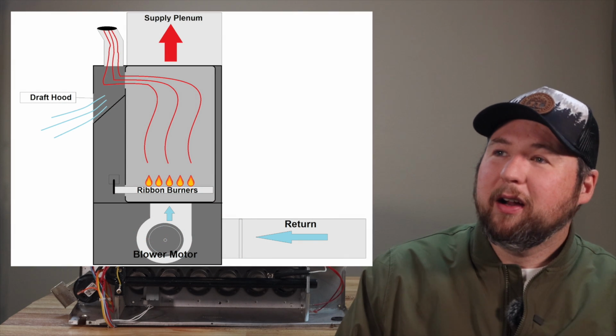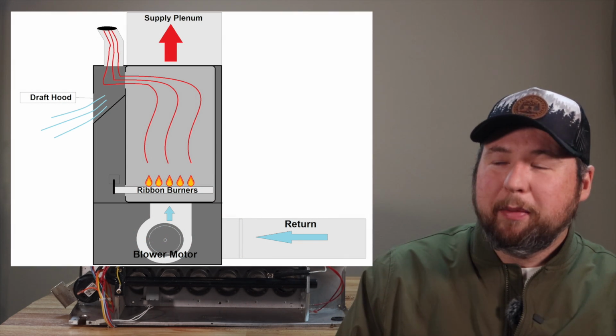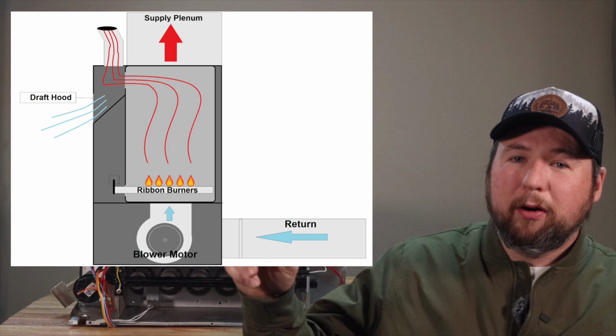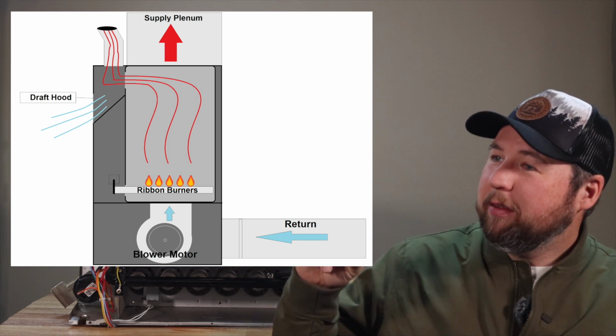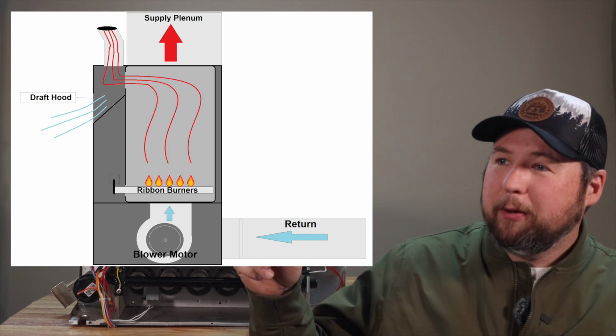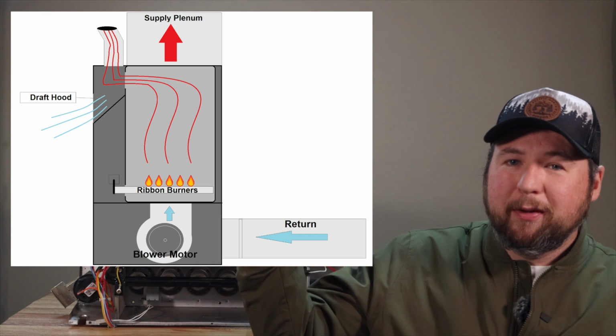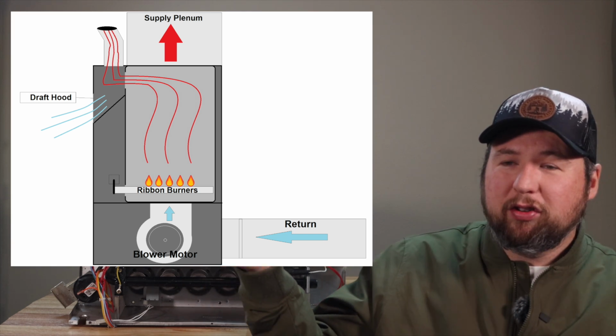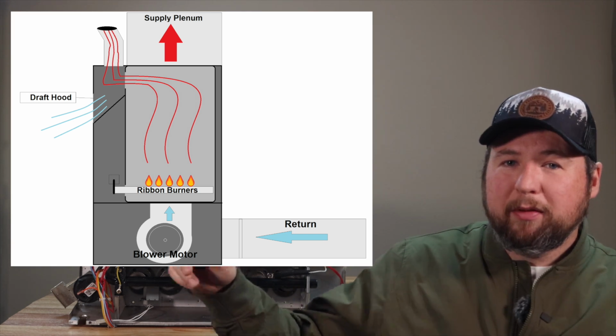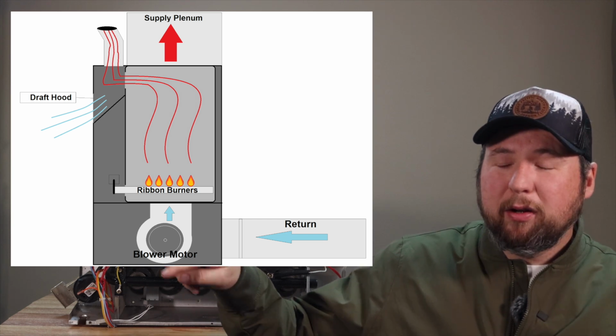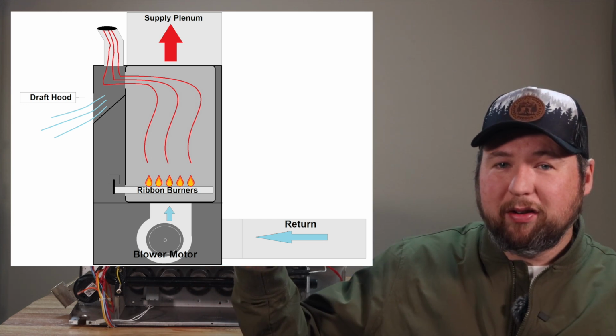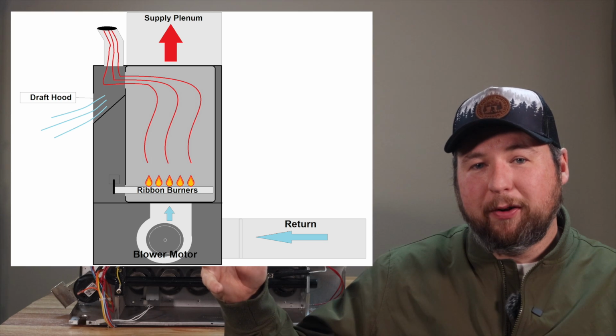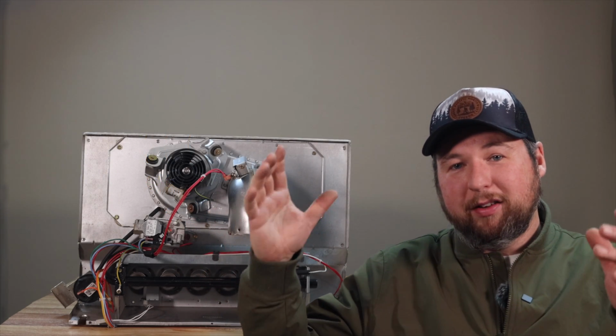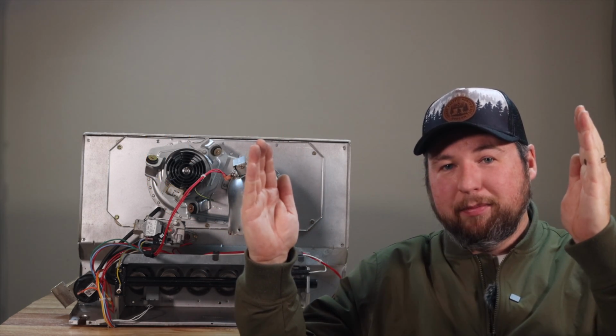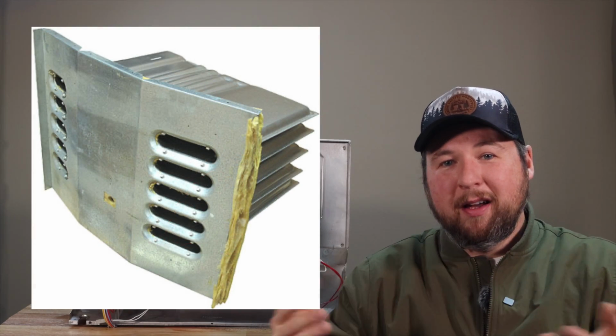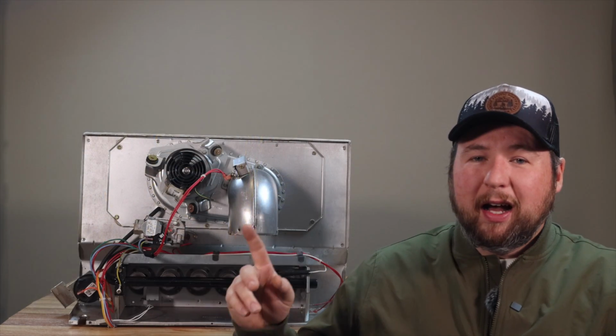So as you can see here, the natural draft furnace basically has the burners. It has a burner or a burner ribbon, and basically it's going to light up, and that heat is going to rise up, and it's going to be heating up that heat exchanger. Now the blower motor, you can see on the bottom, is going to be pulling air from the return. It's going to go across those clamshell heat exchangers. That's the style that they used for natural draft furnaces, is a clamshell, because basically it's just two pieces of metal like a clam shell, right? And put them together, boom, you got a heat exchanger.